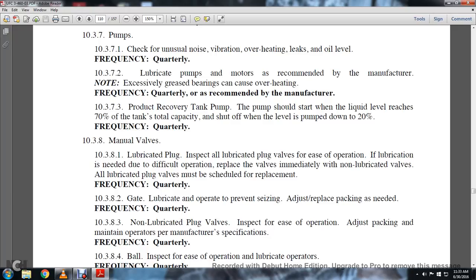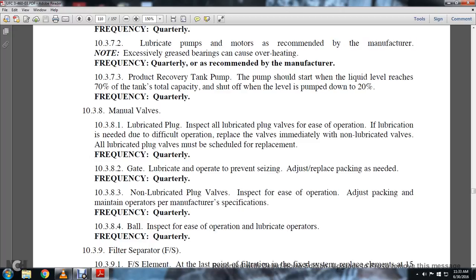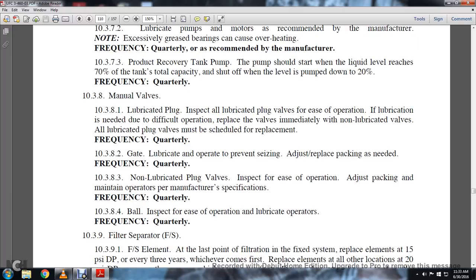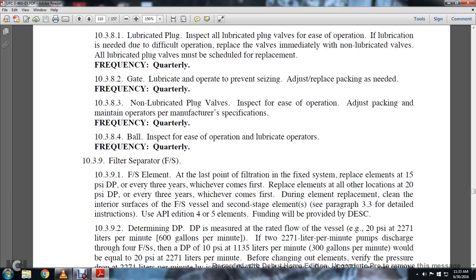Manual valves, gate: lubricate operating parts, preventing seizing, adjusting, replacing, and packing as needed. Quarterly. Manual valves, non-lubricated plug valves: inspect the ease of operation and adjust, pack, and maintain operators per manufacturer specifications. Frequency quarterly. Manual valves, ball: inspect for ease of operation. Lubricate operating parts quarterly.